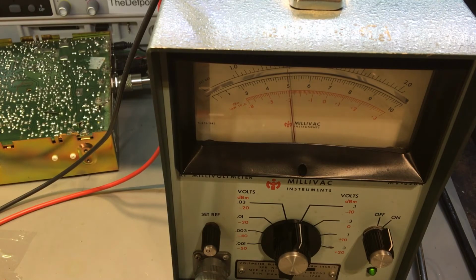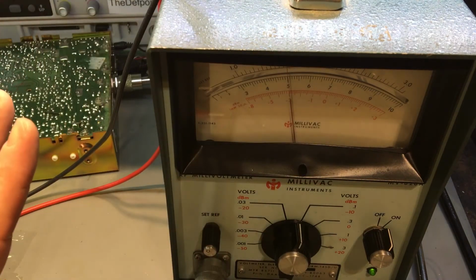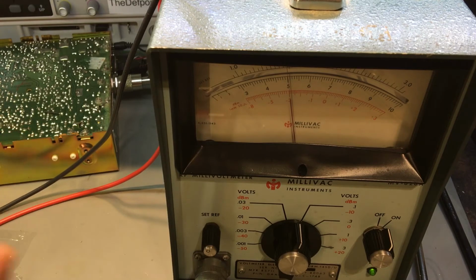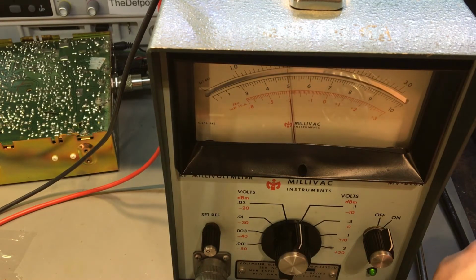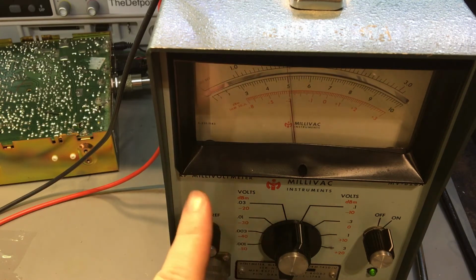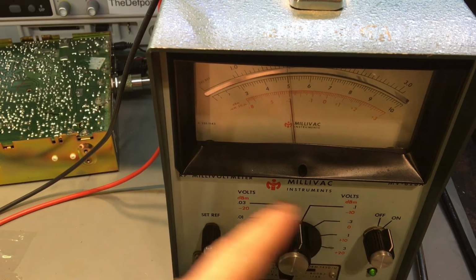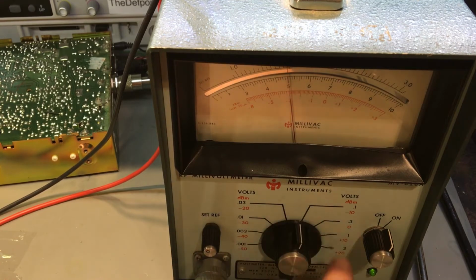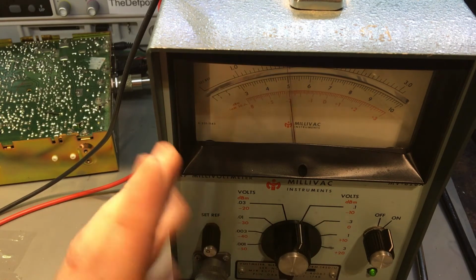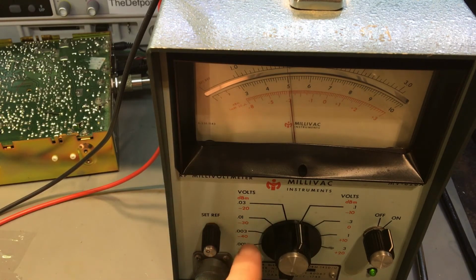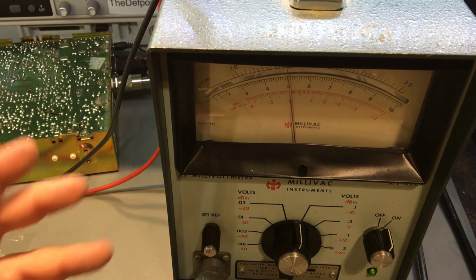So that is working in that sense, so that's pretty good. Now what I've actually found is that these two ranges here, the minus 50 dB and the minus 40 dB, they don't work properly. A lot of it just goes full scale. The other ranges do seem to work with varying degrees of accuracy. It seems these bottom ones aren't as accurate as they should be. At least it appears that way.